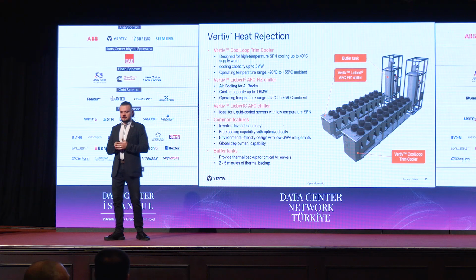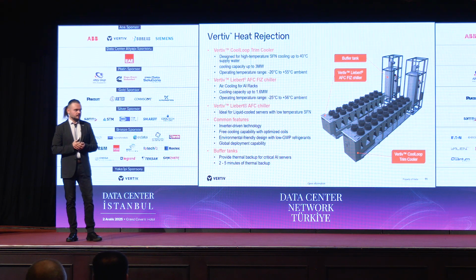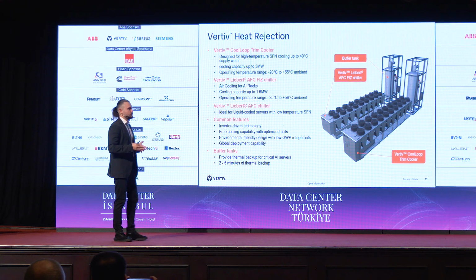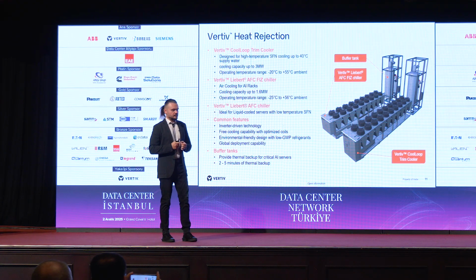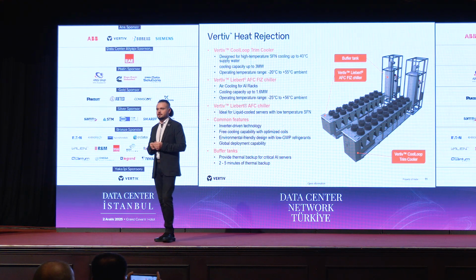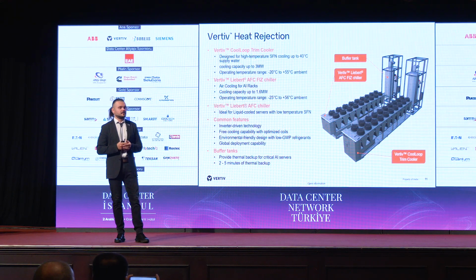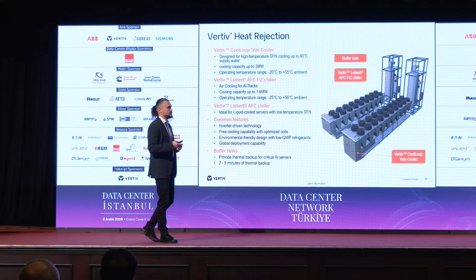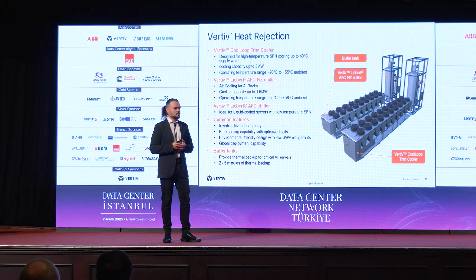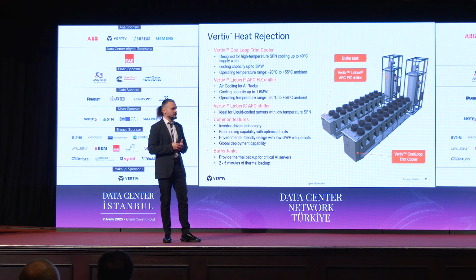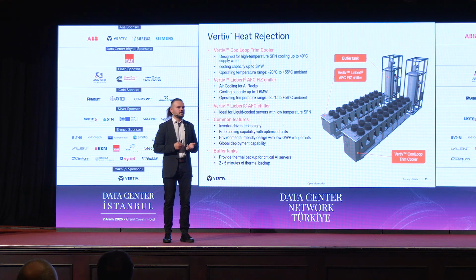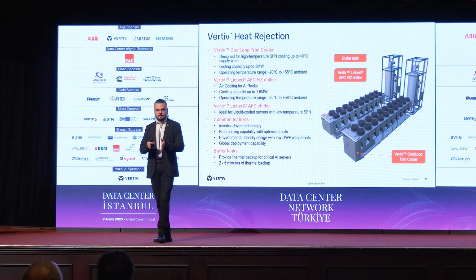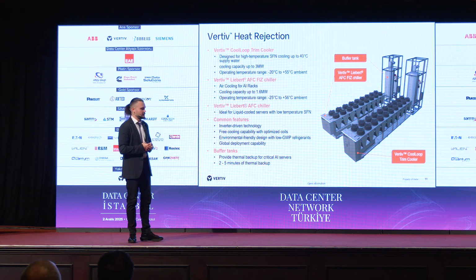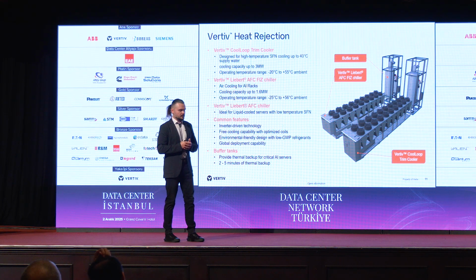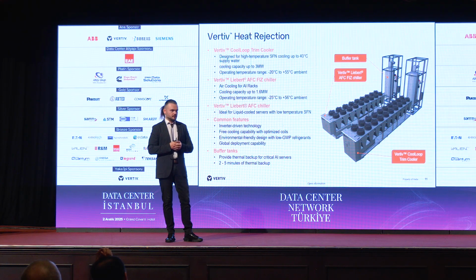What goes outside is two types of chillers. We are dividing the cooling loop into two. That's reasonable, and we are chasing efficiency: for the secondary fluid network, the temperature regime in the water-cooled servers is closer to 40 degrees. We're using a separate loop and a chiller that operates at a 40 degree supply temperature, of water or glycol mix. This unit is a recent development of Vertiv.